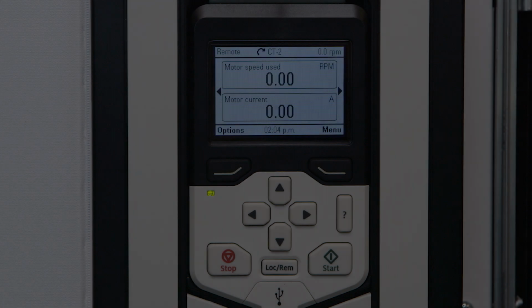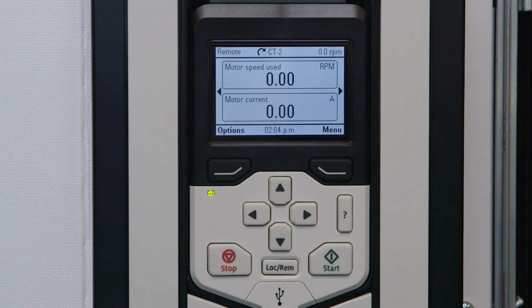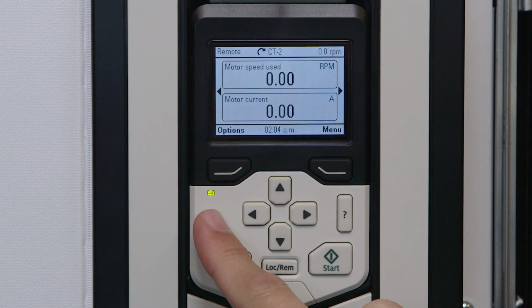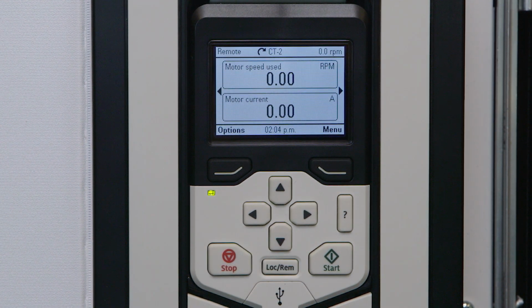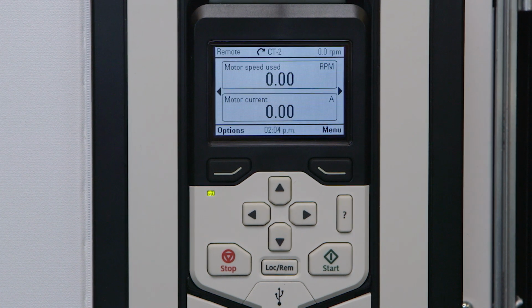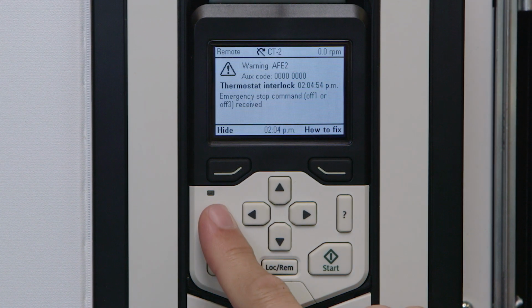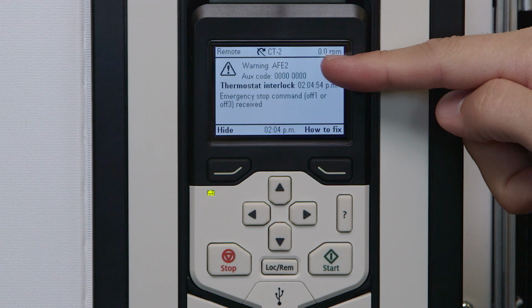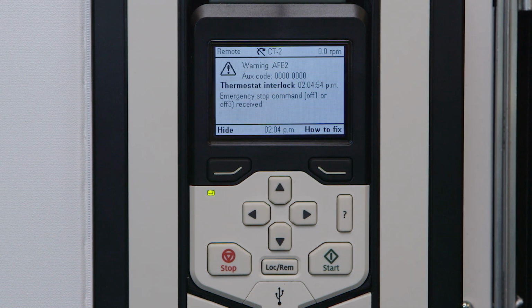Troubleshooting. Now, let's review 4 common startup problems and review troubleshooting to solve them. The VFD keypad LED gives a quick visual of whether or not the VFD is ready to run. A solid green LED is needed to properly operate under all situations. A flashing green LED indicates an active warning. This may still allow operation but may need to be remedied before commissioning is complete.